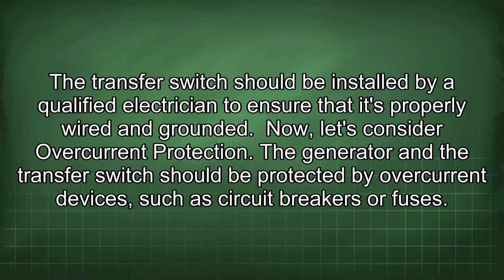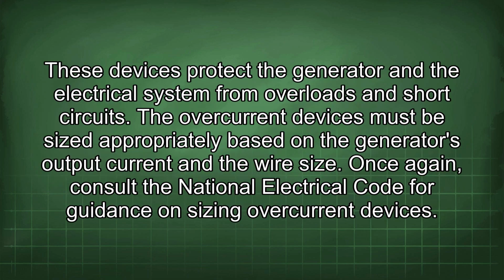Now let's consider overcurrent protection. The generator and the transfer switch should be protected by overcurrent devices, such as circuit breakers or fuses. These devices protect the generator and the electrical system from overloads and short circuits. The overcurrent devices must be sized appropriately based on the generator's output current and the wire size. Once again, consult the National Electrical Code for guidance on sizing overcurrent devices.